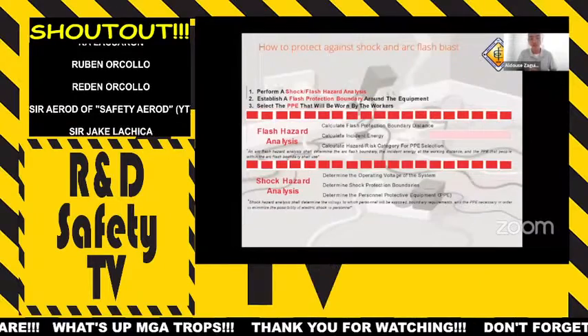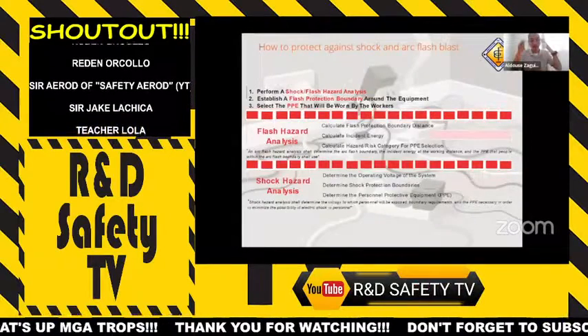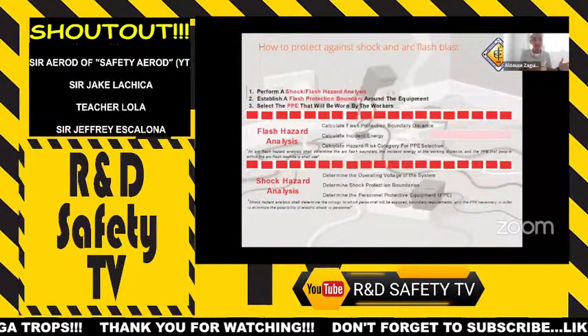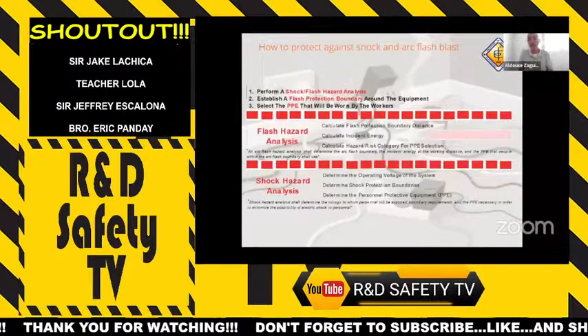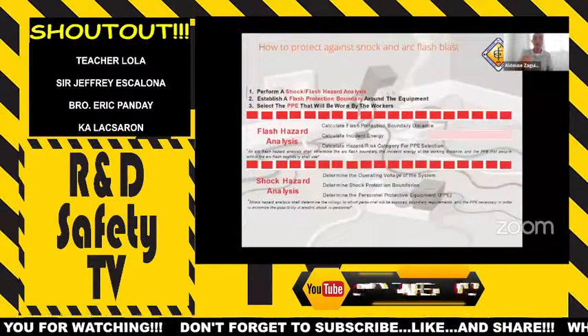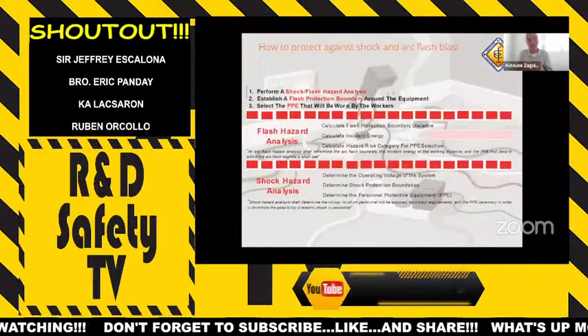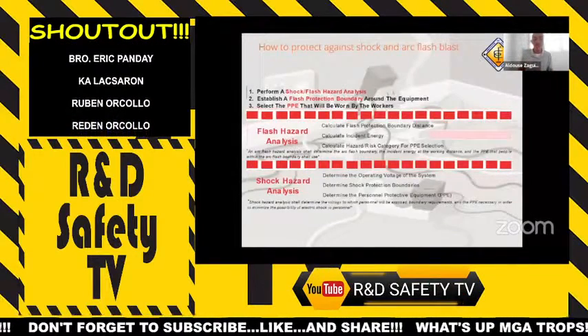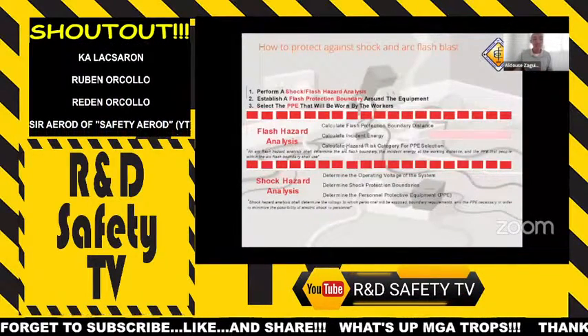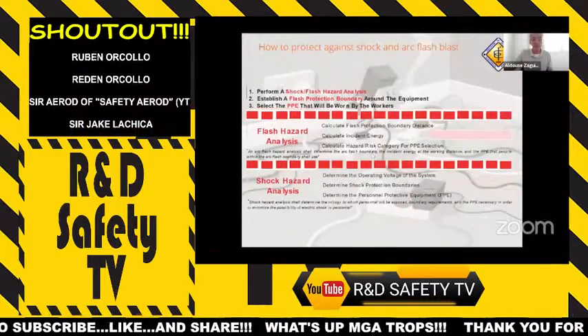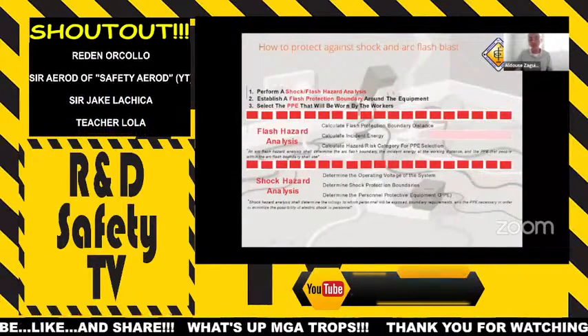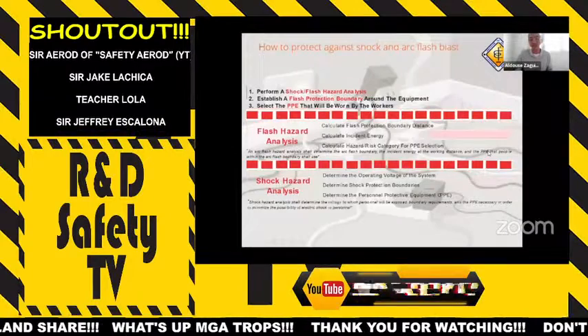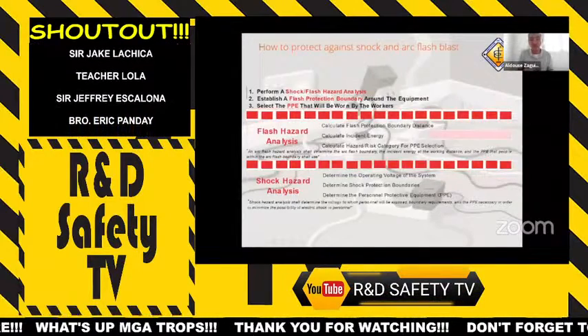It's not just a matter of wearing any arc flash suit and being done — there are ratings involved too. Just like our equipment has kilowatts and kVA ratings, here calories are involved. The flash hazard analysis will tell you the arc flash boundary, incident energy, working distance, and the required PPE, as I've said.